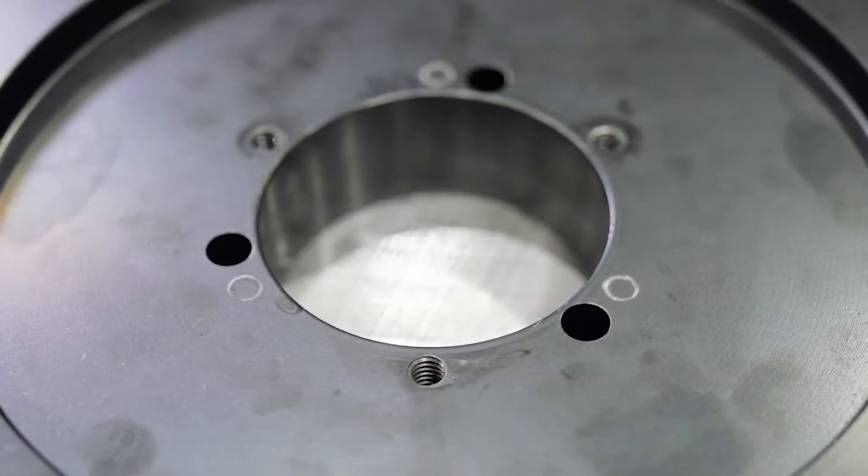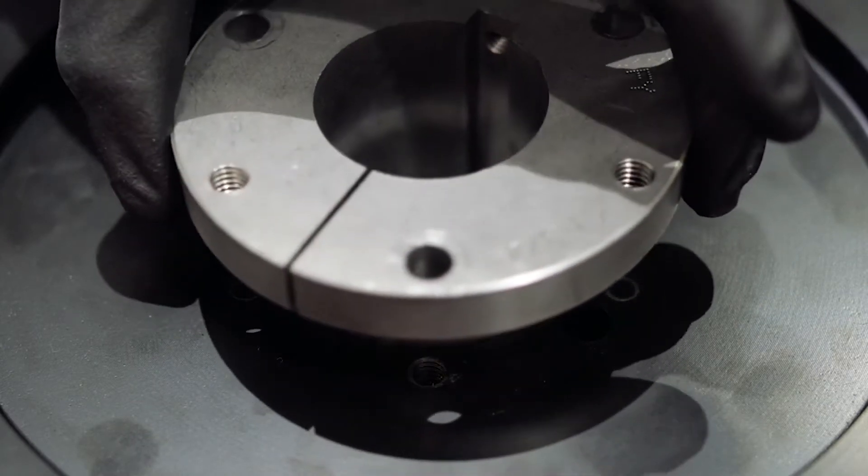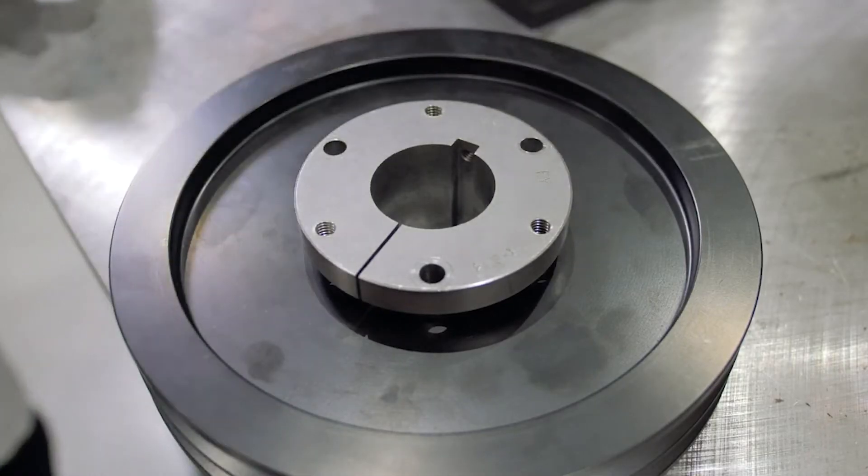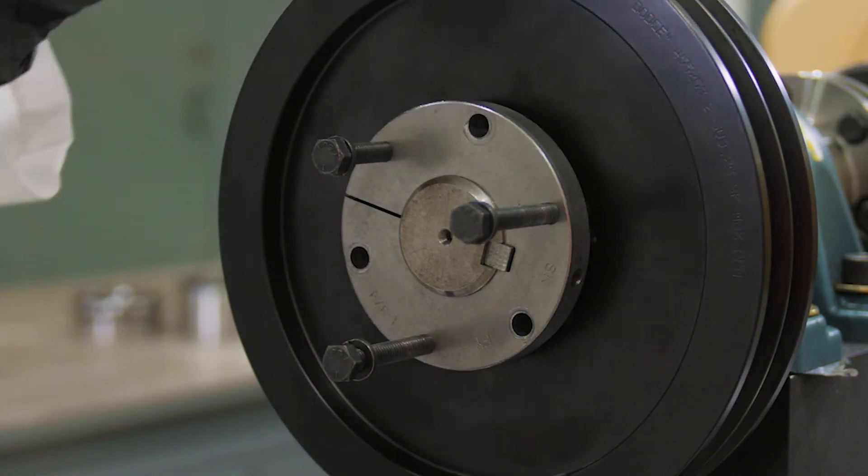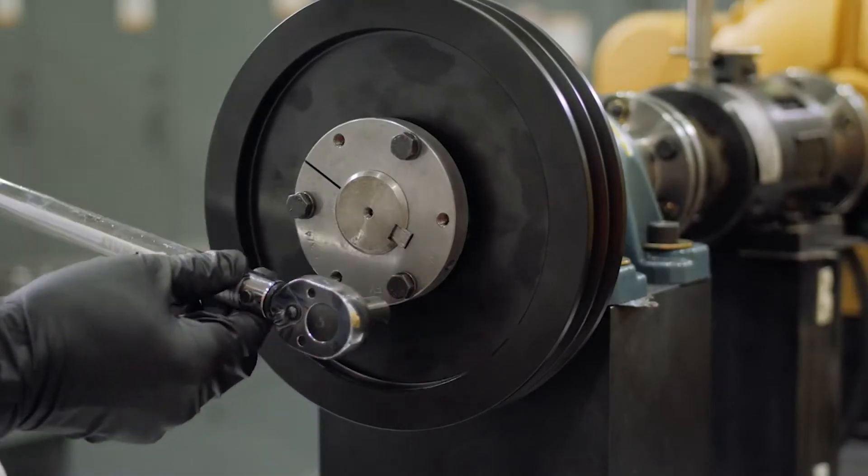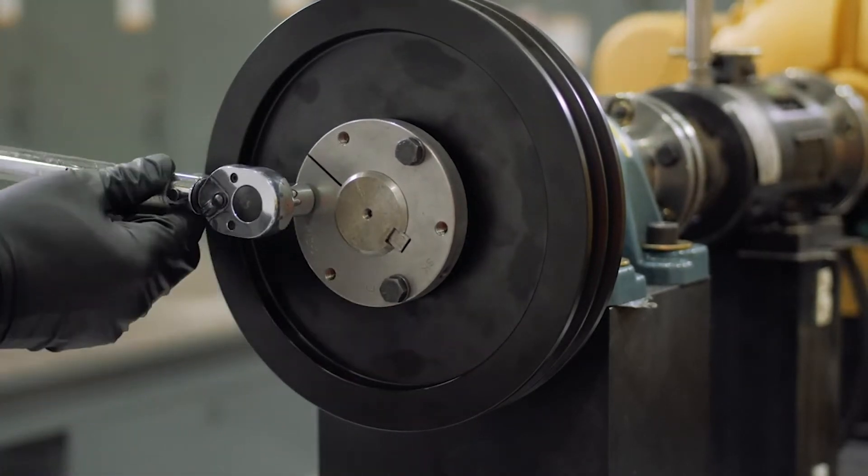Quick disconnect or QD bushings are a concentric shaft attachment method allowing easy installation and removal of V-belt sheaves, sprockets and couplings. This video demonstrates the installation and removal of QD bushings and is a supplement to instruction manual MN4049.